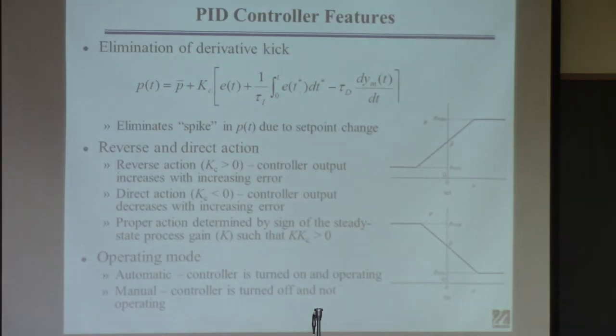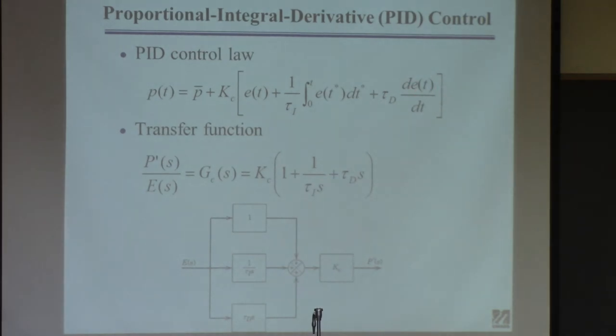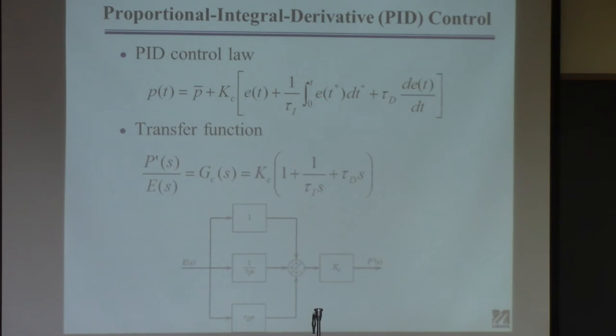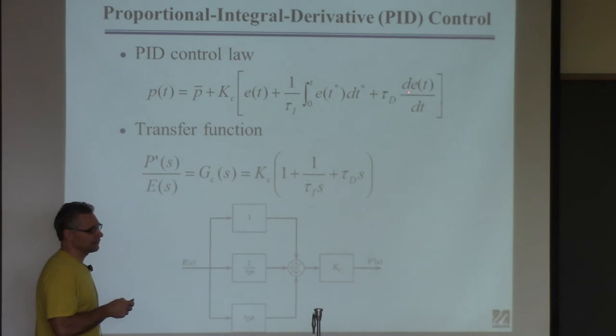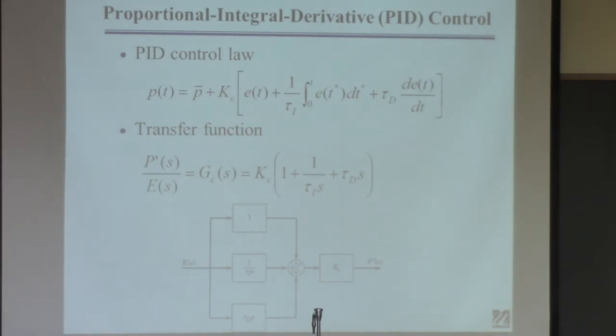What don't I like about PID control? I don't like the D part. When students go to lab with a control project, I tell them to just build PI control and forget the derivative. The problem is: integration is a smoothing operation — integrating a noisy signal smooths it out. Unfortunately, differentiation is the opposite; it accentuates any noise in the signal. Real signals are noisy — the set point you choose isn't noisy, but the measurement from a thermocouple or flow meter is.